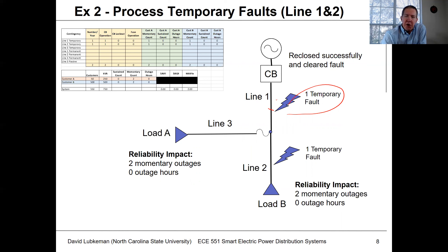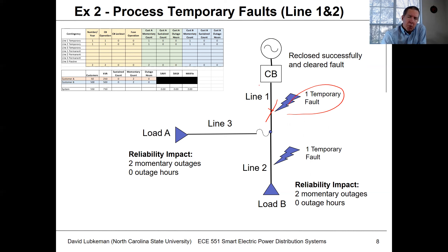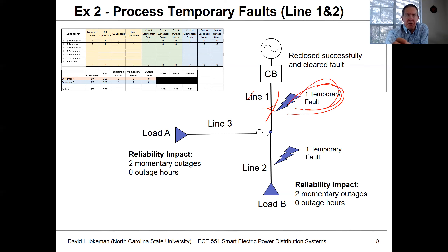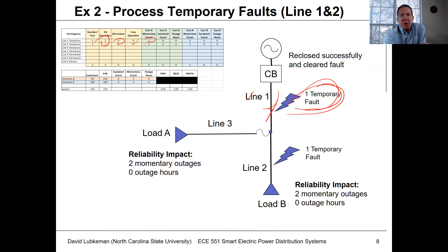If there's a temporary fault, the relay senses the fault current, operates the breaker open, then after a period of time we close the breaker back. If it's temporary, the fault will hopefully be gone. For one temporary fault on line one, the breaker opens and closes — customers at load A and load B see a blink. We get one circuit breaker operation, no lockout, no fuse operation, and we increment the momentary count by one for both customers A and B.